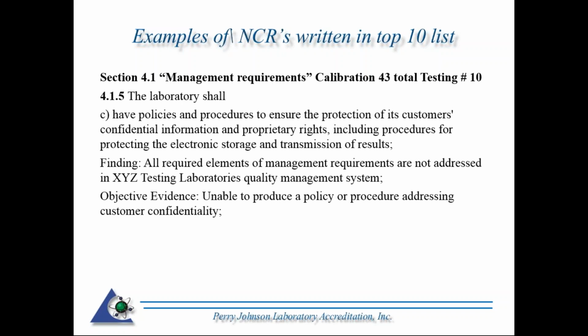The finding was that all elements of the management system are not addressed within XYZ's testing laboratory quality management system. So in this case, say this was a new lab, starting the audit, looking for a policy and procedure for customer confidentiality, the lab was unable to produce a policy or procedure addressing customer confidentiality.